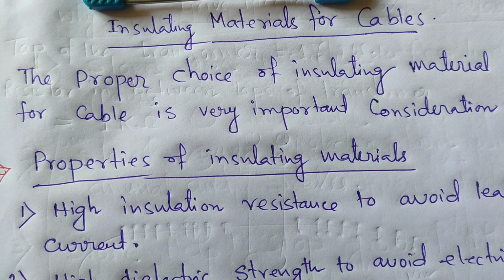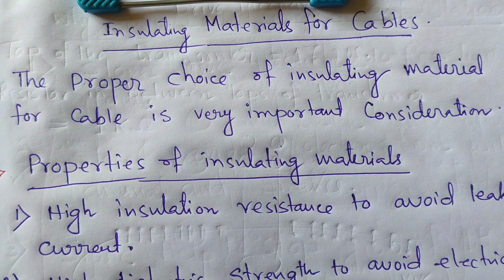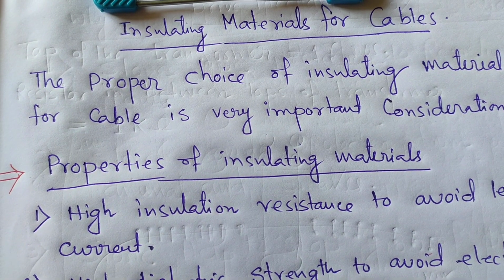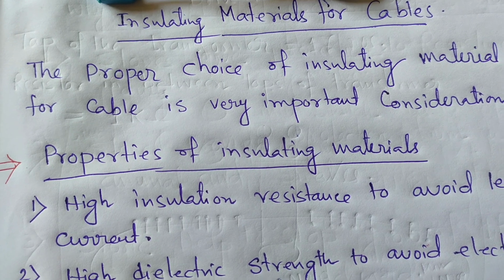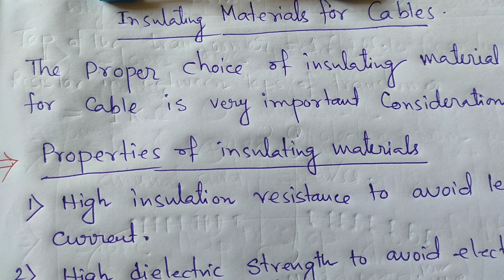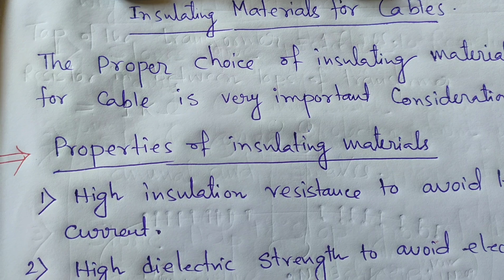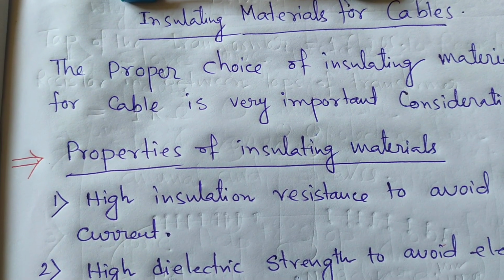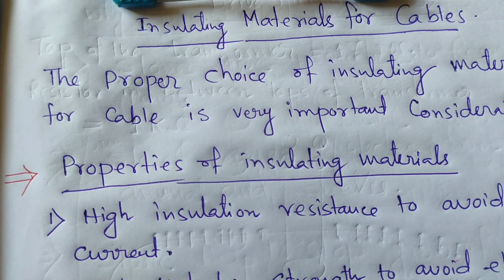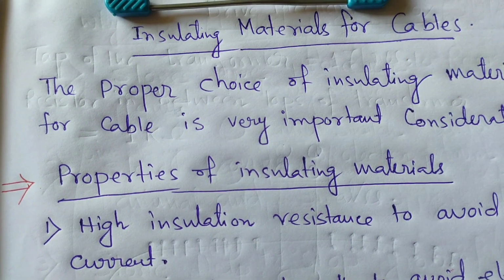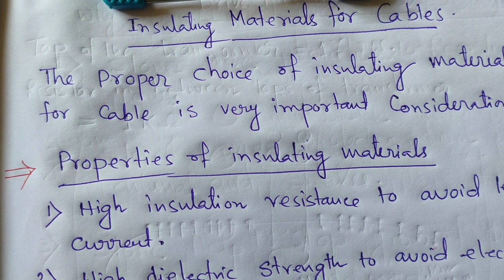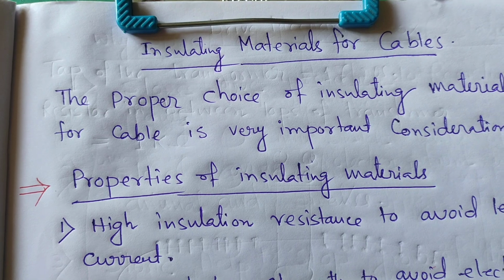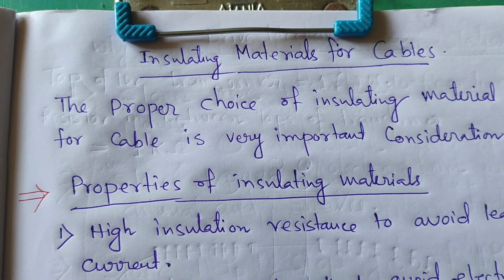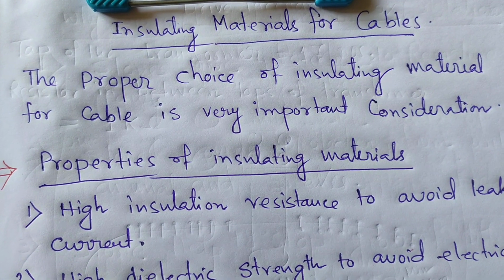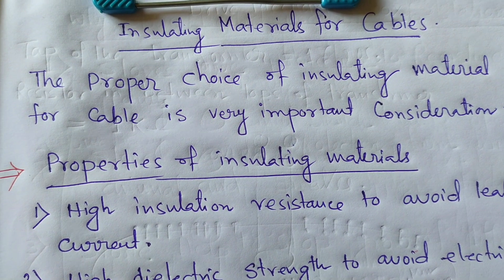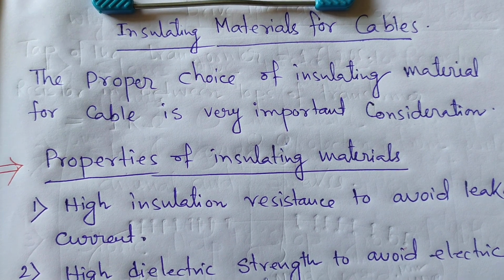Nowadays, insulating material for cable is very important because everywhere we are now using cable for 11 kV, 33 kV, 132 kV, 220 kV and also 400 kV. At different voltage levels we use different types of cables, as per their requirements and specifications, and also depending on the situation and the purpose for which the cable is required, and the quality of the insulation, how much insulation is required for sustaining the voltage. So the proper choice of insulating material for cable is a very important consideration.